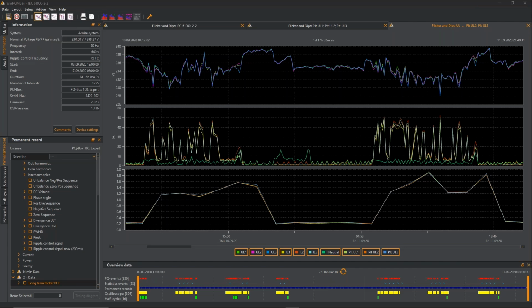But I know that from a physical approach, flicker is caused by quick voltage fluctuations, which in turn are caused by great current changes. Within the 10-minute RMS value, I cannot really see these fluctuations. So I want to go more into detail. I want to see the minimum and the maximum values of the voltage and the current, as well as a higher resolution of the flicker.